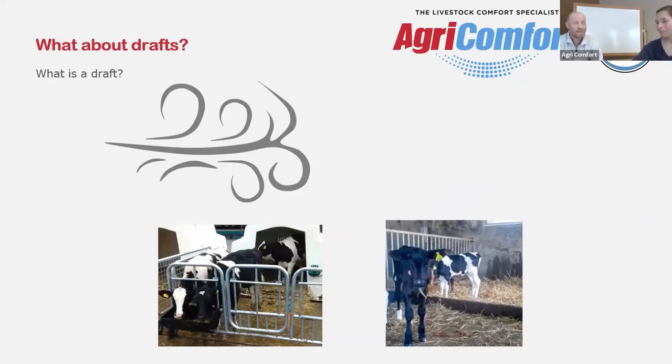Yeah, so drafts are the single most commonly misunderstood thing in ventilation of anything that I deal with. There's a couple ways to define a draft, and I think what we would probably all agree is, in general, when a farmer says the word draft, they have a negative connotation to it. Okay, so really a draft is just a speed. By definition, a draft is airflow on a baby calf that is greater than 50 feet per minute of speed.